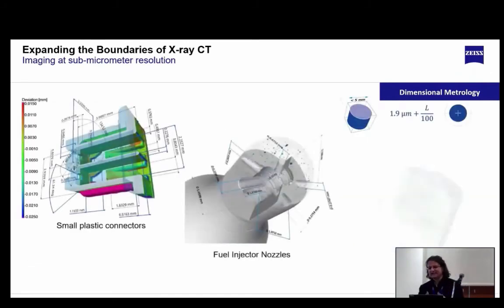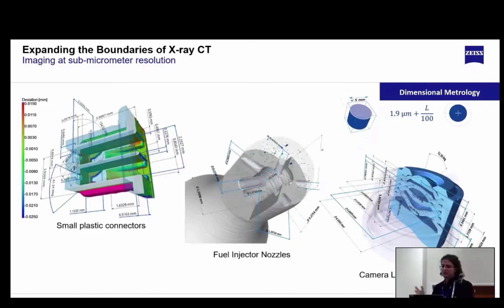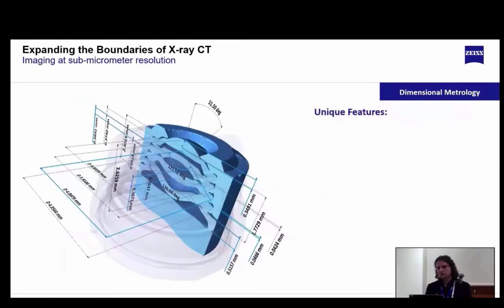And there are other examples in which the metrology extension could be applied. For example, for checking small plastic connectors, as-made to part comparisons, and fuel injector nozzles, which, if you are familiar with them, have very tiny holes that are also very difficult to scan, impossible with a tactile probe or an optical system that you can find in the traditional market. So X-ray CT is a nice solution, and to be able to guarantee that those measurements are accurate, if you use this workflow with the metrology extension for the X-ray microscope, then you can trust the measurement.